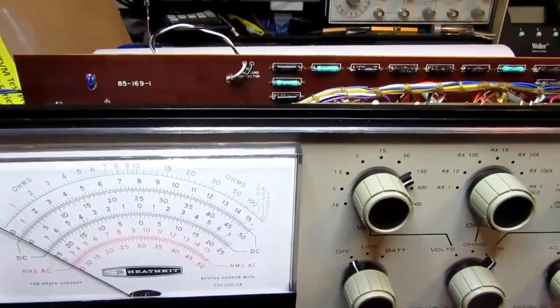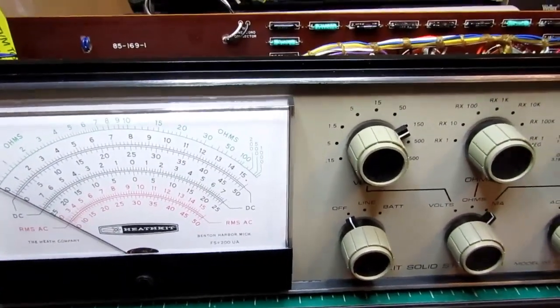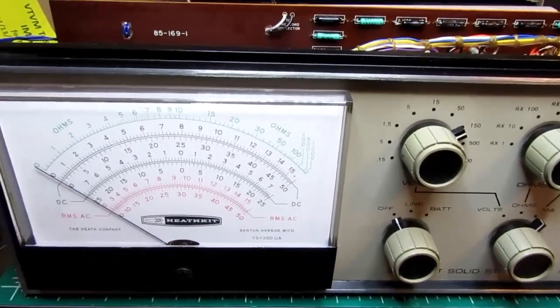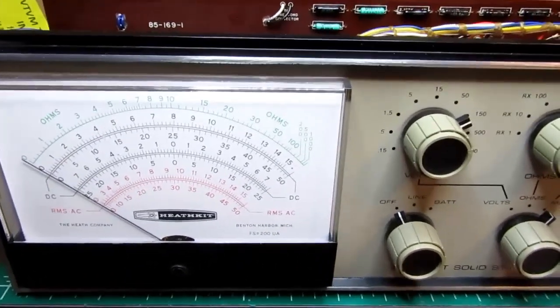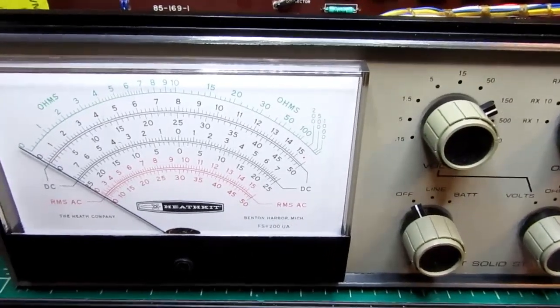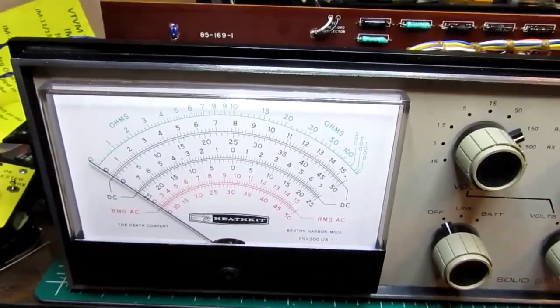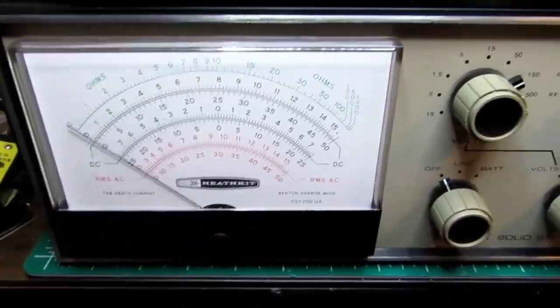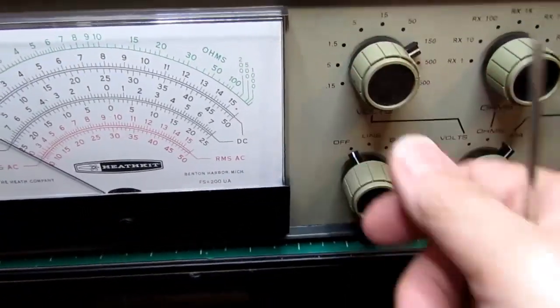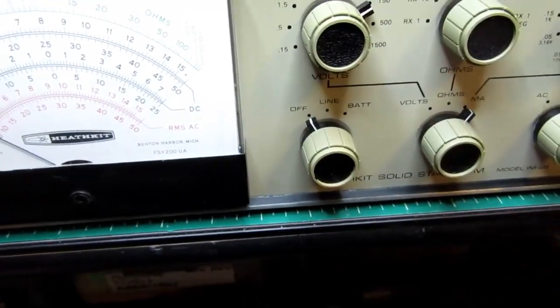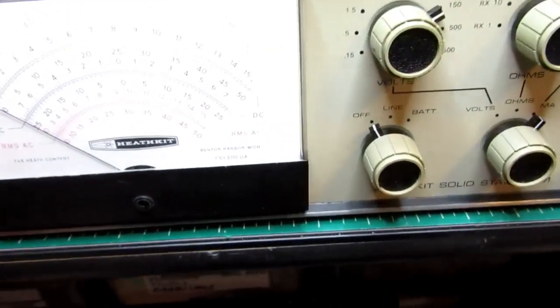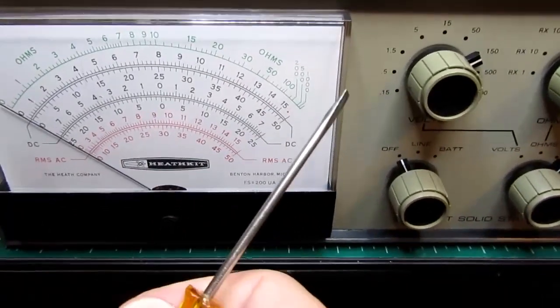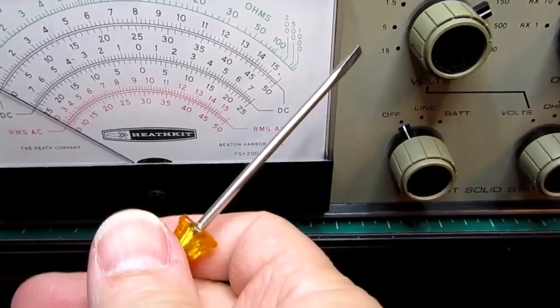One of the most common problems I've seen with these meters, and actually I think every one I've worked on out of the several I've done, all had the same problem out of the box. As soon as I would receive them from the thrift store or the eBay seller or wherever I'd get them, you'd plug it in, you'd put it in voltage mode, and you'd set it to some value, or some range, and you'd hook the test leads up, make sure it's the right kind of test lead, and turn it on, and the meter goes prang really hard over to the right hand side and just pegs. It's like way over here past the scale.